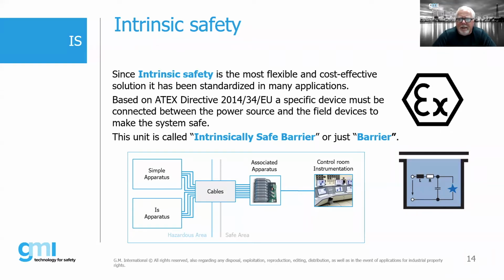So an intrinsically safe circuit, in effect, is a combination of your field device, could be a simple apparatus, your cables, your associated apparatus, which is what we also use as a term for intrinsically safe barrier, and our control room instrumentation of some sort. So that is what is considered to be our loop, and that's a system concept.